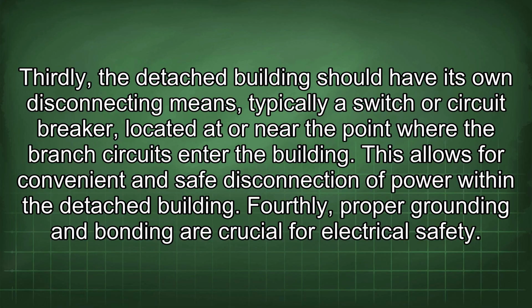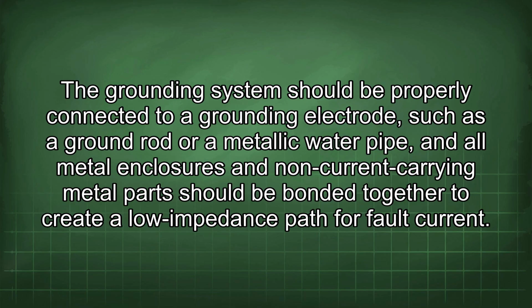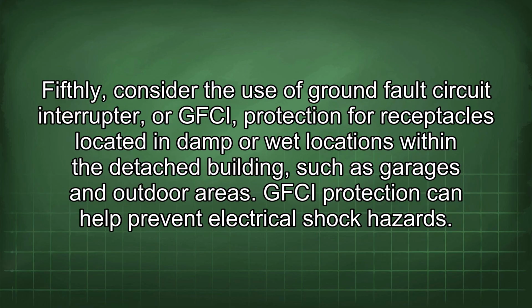Fourthly, proper grounding and bonding are crucial for electrical safety. The grounding system should be properly connected to a grounding electrode, such as a ground rod or a metallic water pipe, and all metal enclosures and non-current carrying metal parts should be bonded together to create a low impedance path for fault current. Fifthly, consider the use of ground fault circuit interrupter, or GFCI, protection for receptacles located in damp or wet locations within the detached building, such as garages and outdoor areas. GFCI protection can help prevent electrical shock hazards.